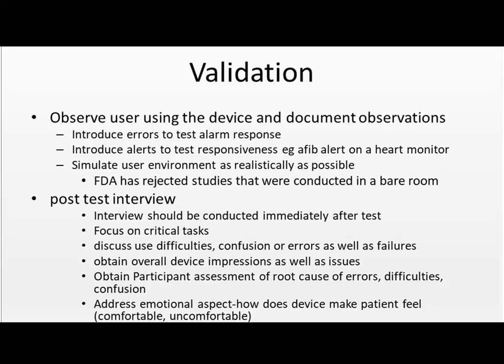Following the test, there's a post-test interview of each participant. The interview should be conducted immediately after the test. You want fresh thoughts, fresh observations. The interview should focus on critical tasks. You should discuss difficulties, confusion, errors, as well as failures. You should obtain an overall device impression as well as discuss the issues.